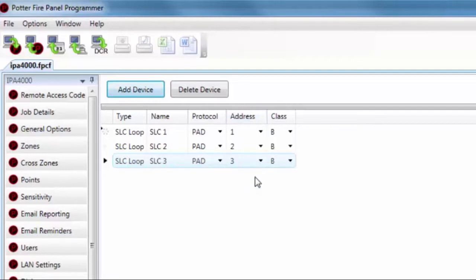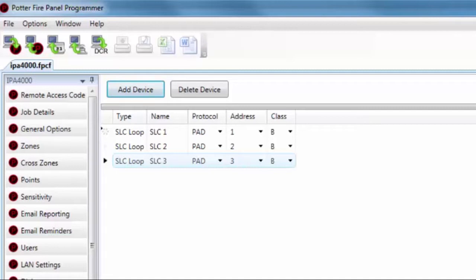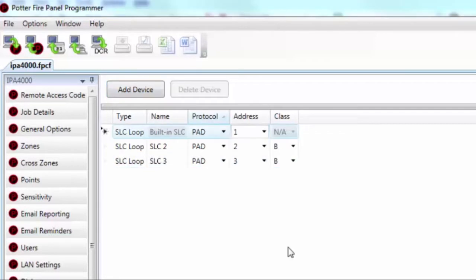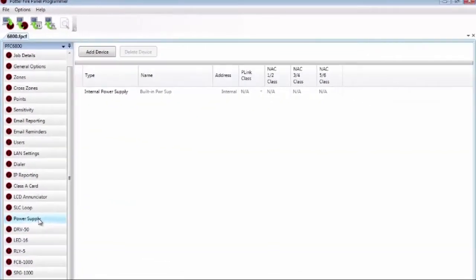In the Address column, for every expansion card installed in the field, the address shown here must match the address on the DIP switch of that card. You can also designate whether the SLC loop will be wired Class A or Class B — the default is Class B. The class of wiring for the internal SLC is set via the Class A card programming window. Each expansion card has return terminals to allow for Class A wiring. To program the points on the SLC expansion cards, go to the Points programming tab.